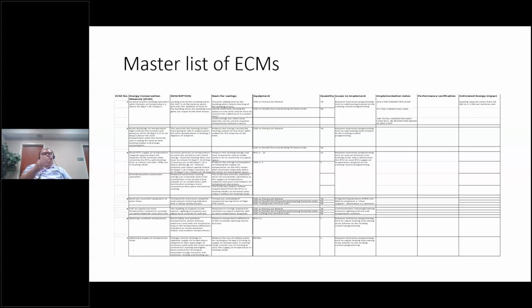I describe the system, I describe the ECM, and put in some idea of how it was implemented and how you know it's going to work, what you look for as success, and how you're going to verify that success. You can use the IPMVP, that's fundamental. But if you come up with another way, like logging before you implement and logging afterward, you log the operation of the pump over a certain amount of time, implement the ECM, then log it again afterward. The difference shows you've improved the situation, improved performance, reduced energy, whatever your goal was in that ECM. You have it noted here how you prove that performance, and keep that everywhere you go, so you don't have to keep reinventing the wheel.